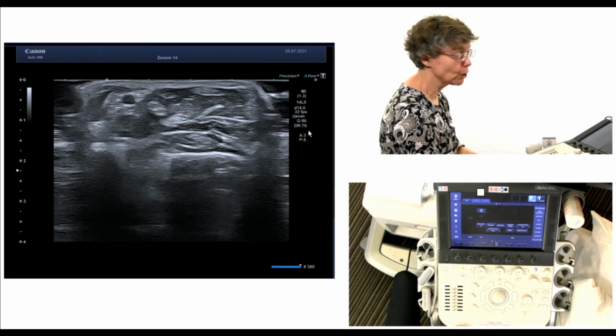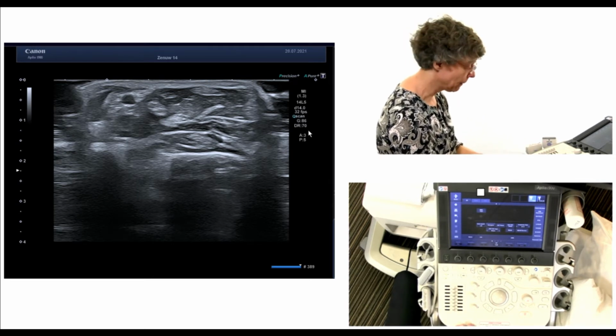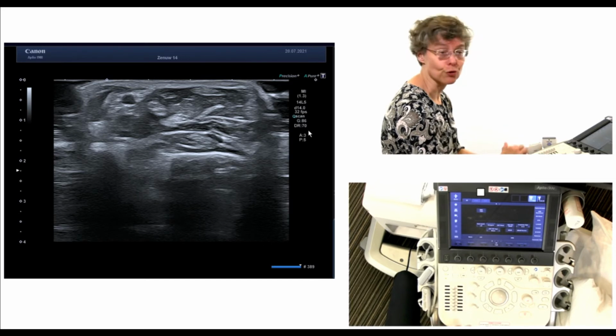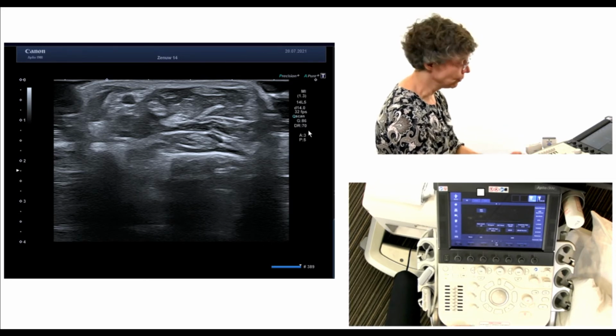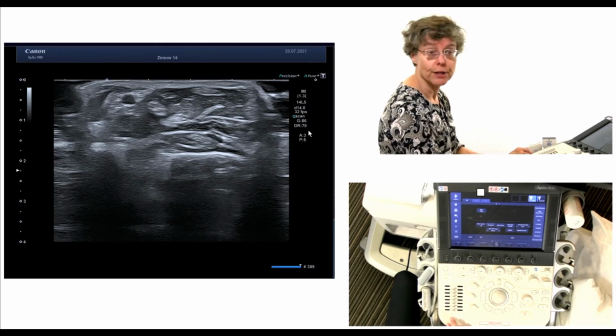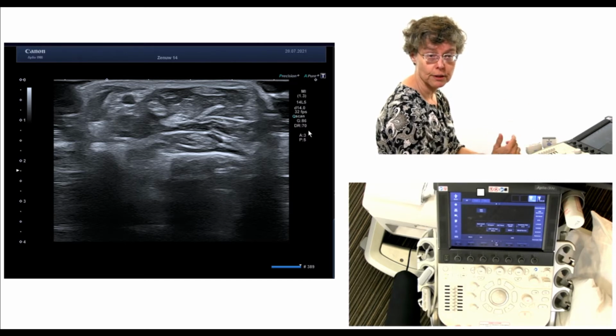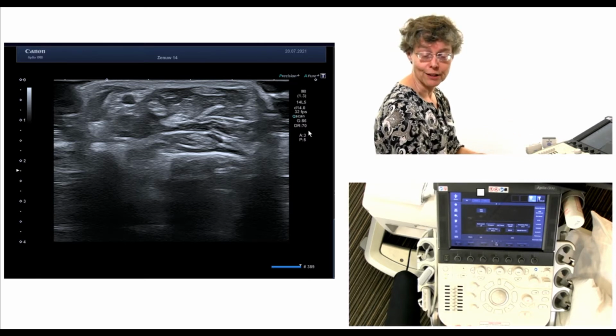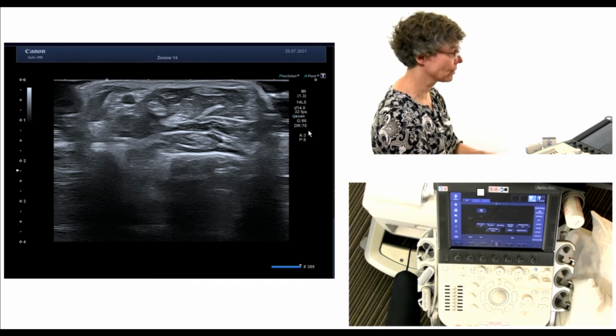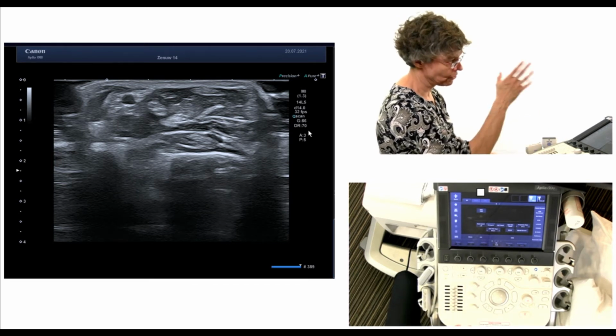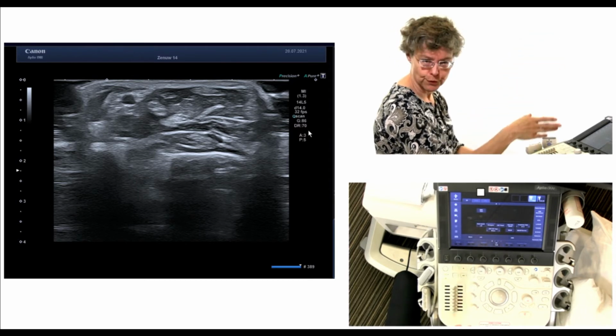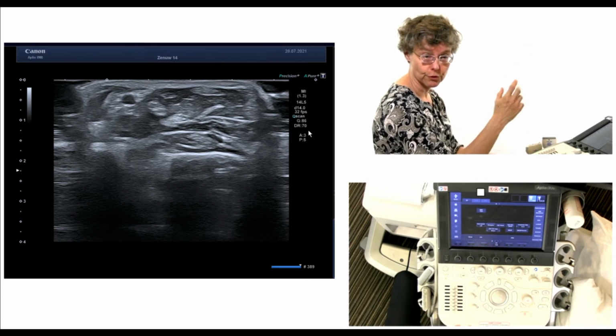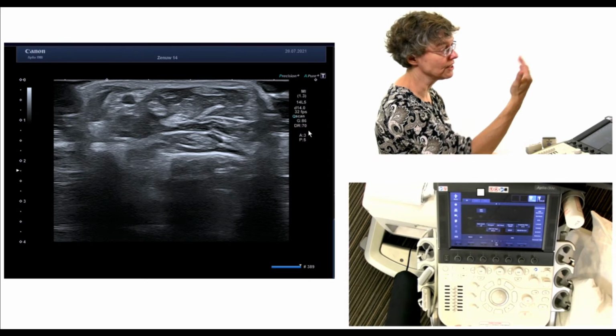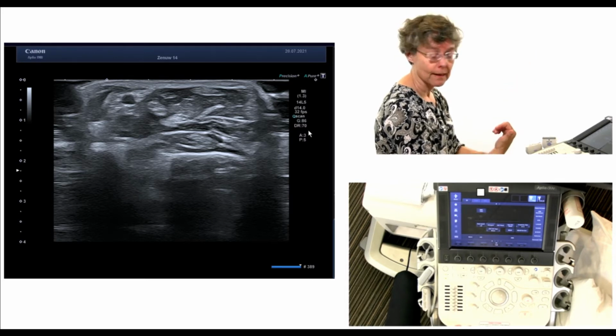We talked about the overall gain, so the volume knob, but these are called time gain controls. What they do is let you adjust the gain very specifically for a certain depth. Now, why is it called time gain control and not depth gain control, which would make a little more common sense? It is because the machine thinks that the longer it takes for the signal to return to the probe, so the reflection to return to the probe, the deeper it will originate.